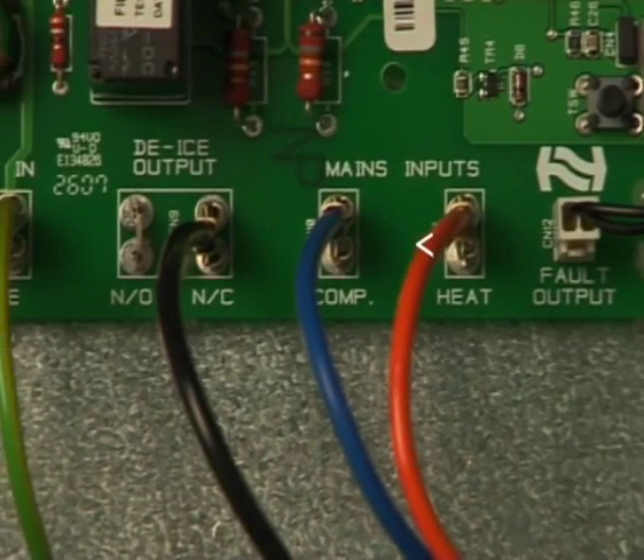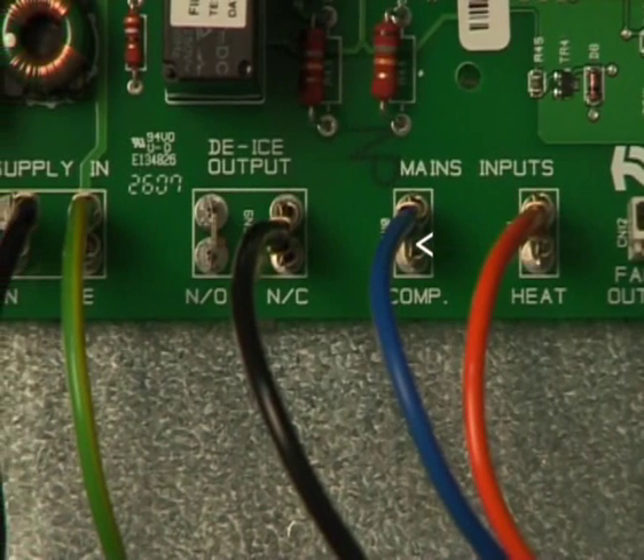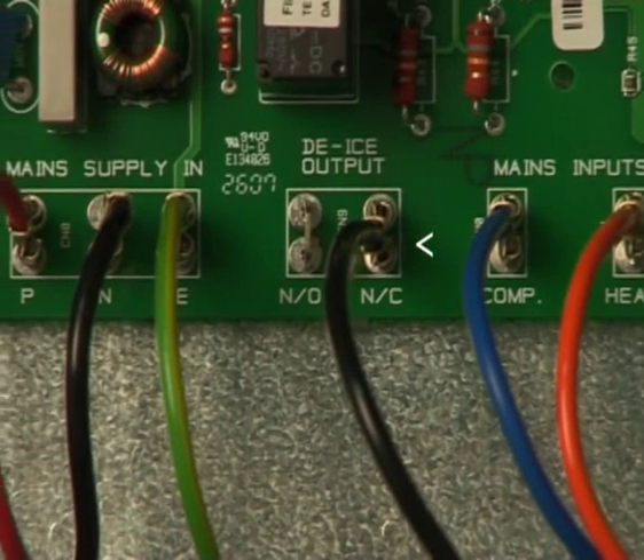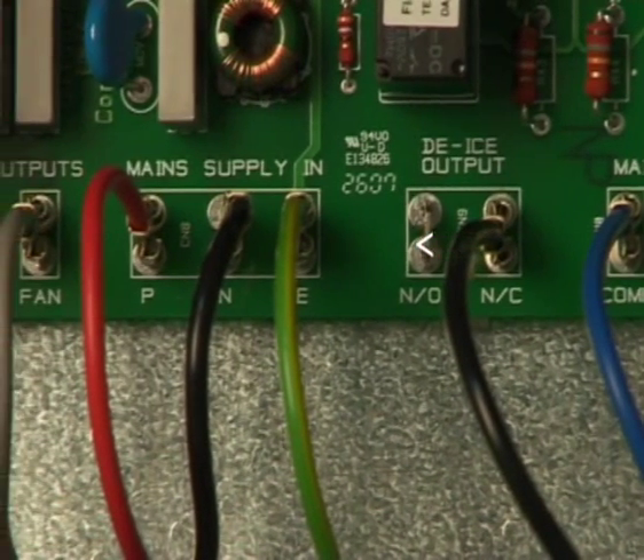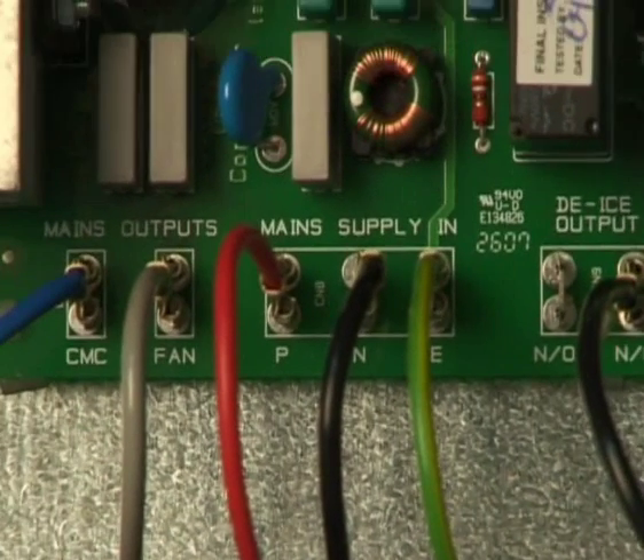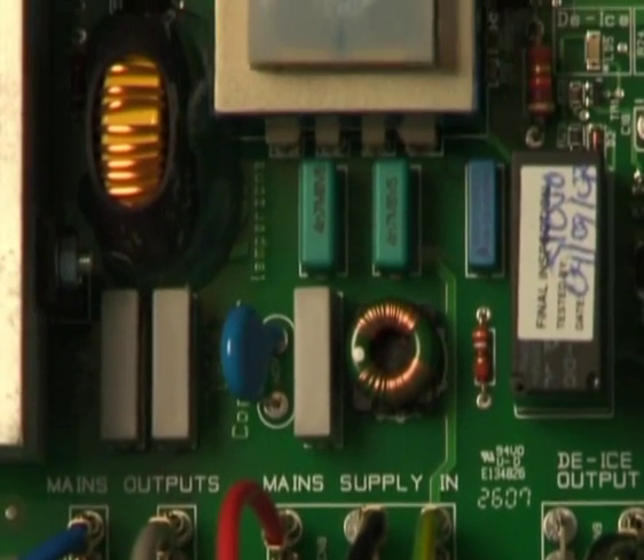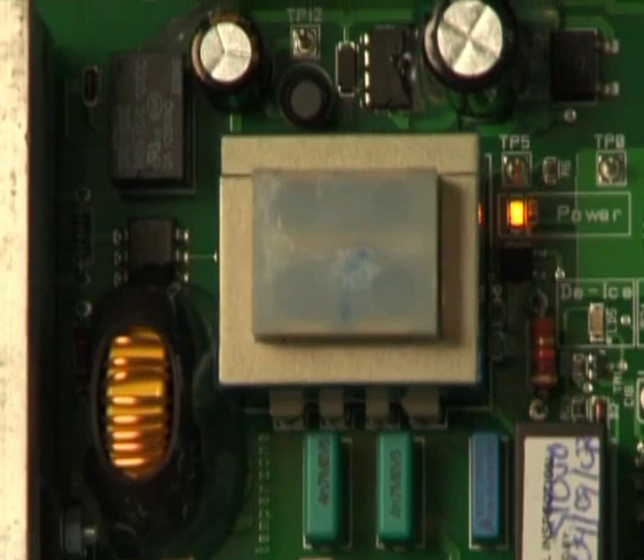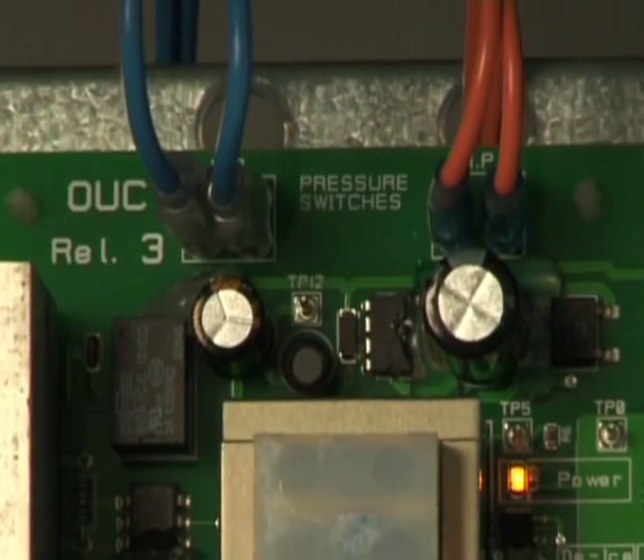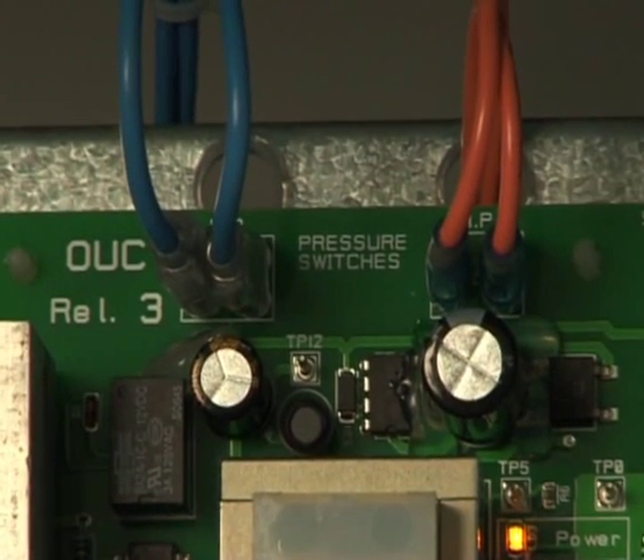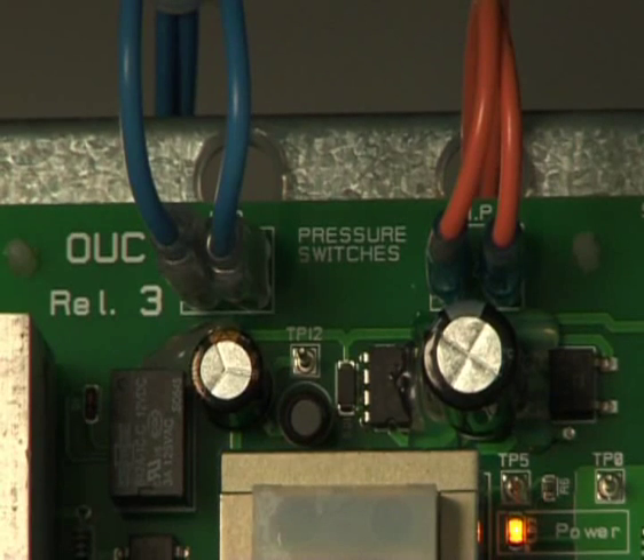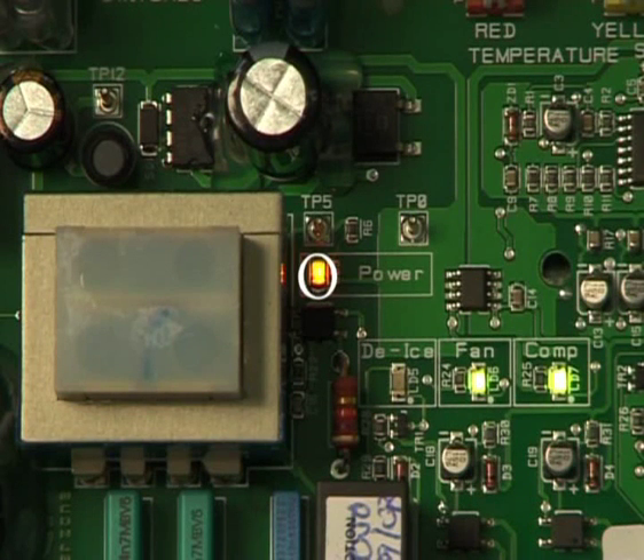The OUC connects to mains power via the unit's control circuit, and through signals received from the thermostat, initiates the compressor and condenser fan according to system status. High and low pressure safety switches connect directly to the OUC and are direct acting. An amber LED in the centre of the OUC informs that power is connected to the OUC.